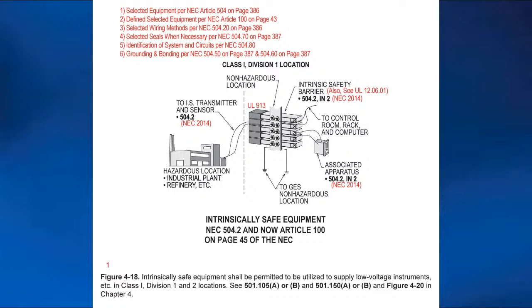Then the identification of your systems and circuits, as you said, is 504.80. And I believe A is your terminations, which would be light blue. And then B is your wiring method. And then when you go to C, you get your color coding of a cable, or if your conductors happen to be in a conduit, every 25 foot. Okay. So that is basically 5. Now 6 is grounding and bonding, and that's 504.50 on page 387, and 504.60 on page 387. And that's exactly how most of the engineers that I've talked to, installing electricians and the inspectors, approach inspecting these systems. If we're all on the same page, and it doesn't necessarily have to be in that order, just as long as you perform steps 1 through 6, you do a decent job when you're installing these intrinsically safe systems.